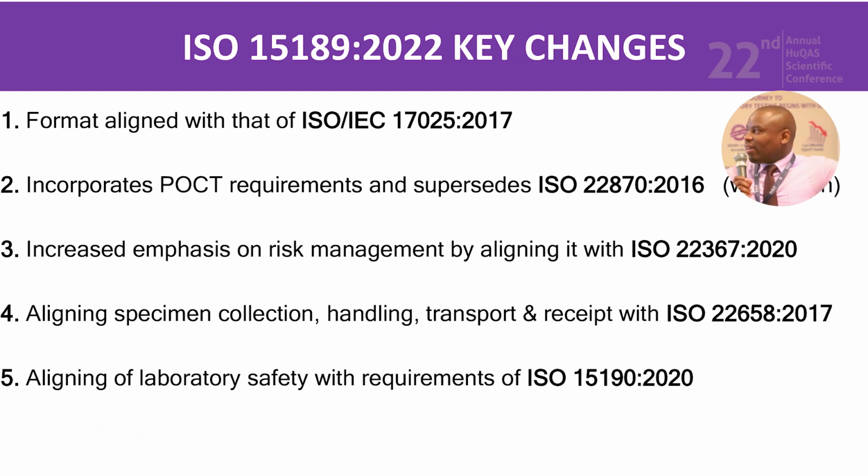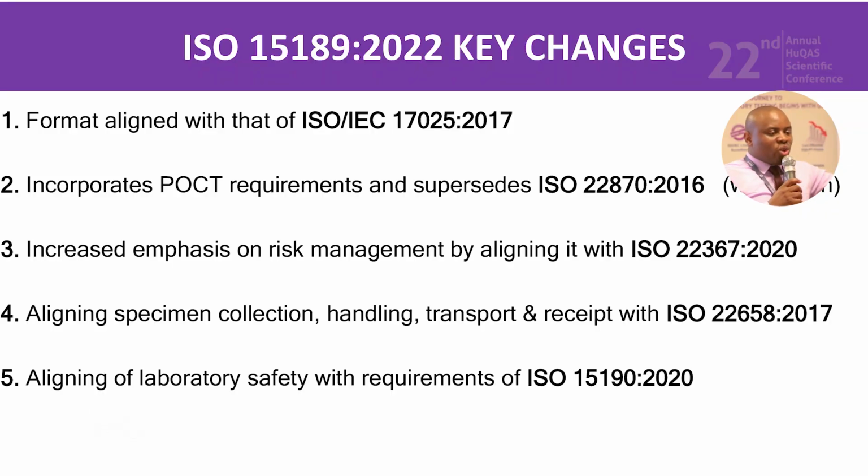Then secondly, you have the incorporation of POCT requirements. You may be aware that we used to have an ISO standard for point of care testing. Now that standard, you may not hear about it again once the transition to 15189:2022 is completed, because all those requirements in ISO 22870 have now been moved to a new version of the standard. You'll also notice an increased emphasis on risk management.